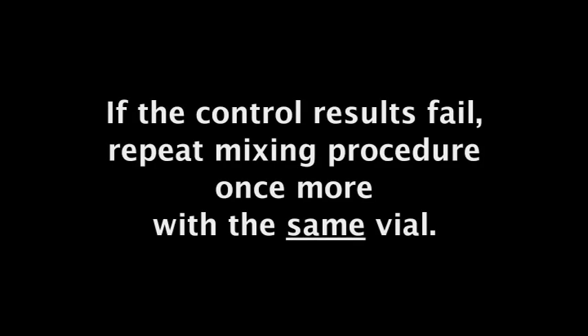If done correctly, the synthetic control will yield the correct values found on your assay sheet. If it does not, please repeat this procedure one more time using the same vial. After two failures, please open a new vial and test again.